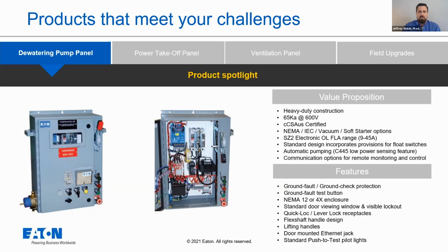All of our assemblies that I'll be talking about today have been tested and marked with the cCSAus insignia, which means CSA has also tested them to the UL standards, so they can be used on either side of the border. The starter includes ground fault and ground check protection relay for dealing with trailing cables, and the units are available with a number of our contactors. So if you wanted an IEC contactor or a NEMA contactor or a vacuum contactor, that's all available as a technology that we can include inside the enclosure.